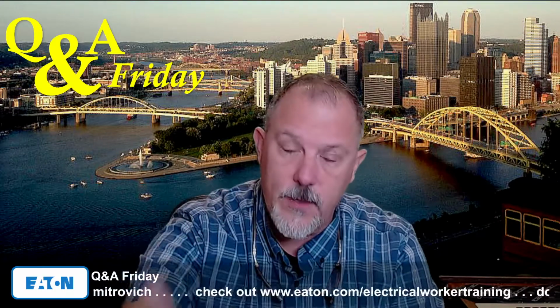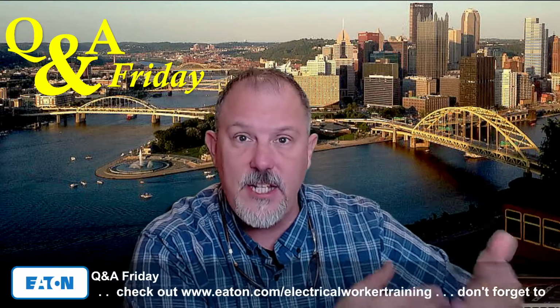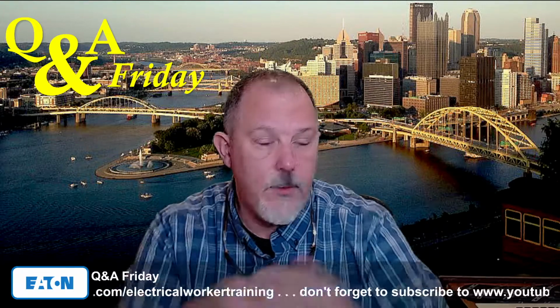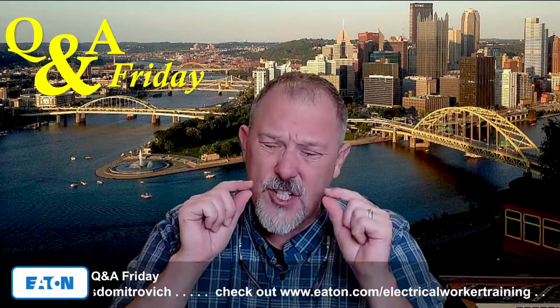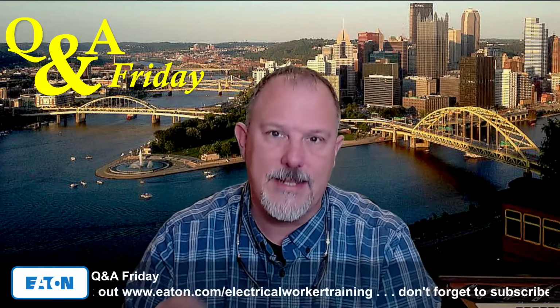Identical? No. Siemens will do it different than Square D. Square D will do it different than GE. GE may do it different than Eaton. I wouldn't say any one of those are the right way. You get the data that you need to help troubleshoot these circuits, but look at the trip codes, look at the LED lights. Some will have more trip codes than others, but leverage those technologies, and just remember they're different between manufacturers. It's not driven by a standard.